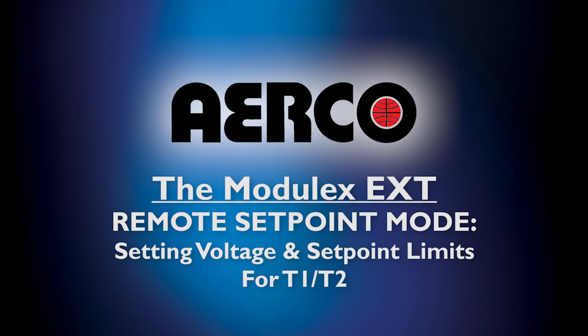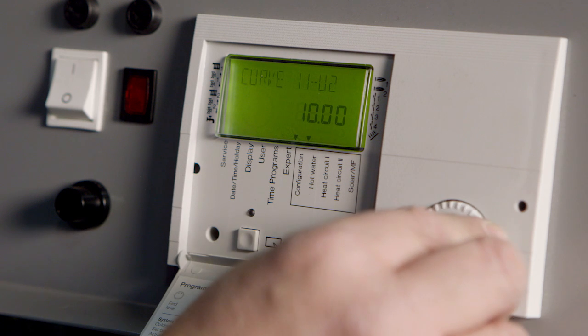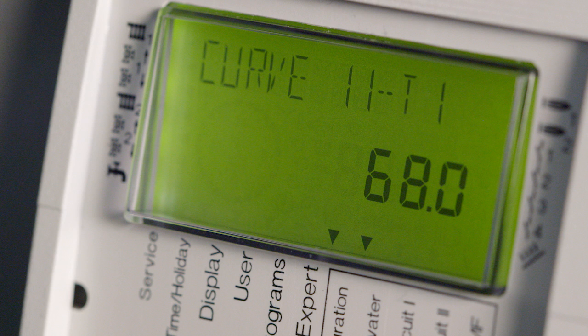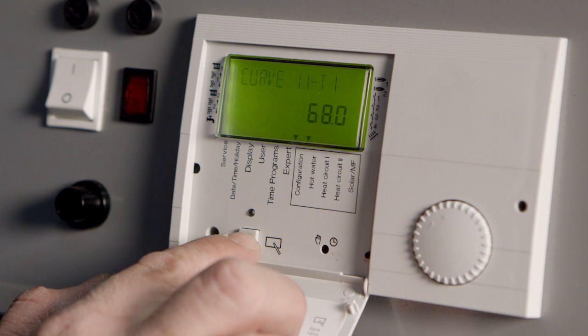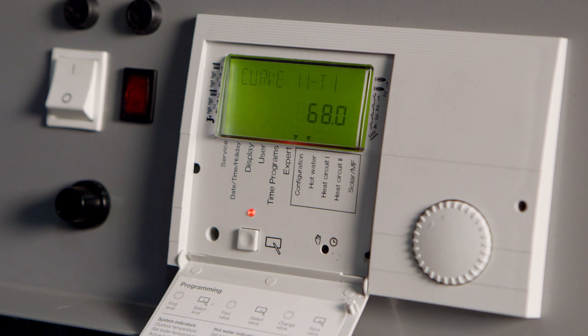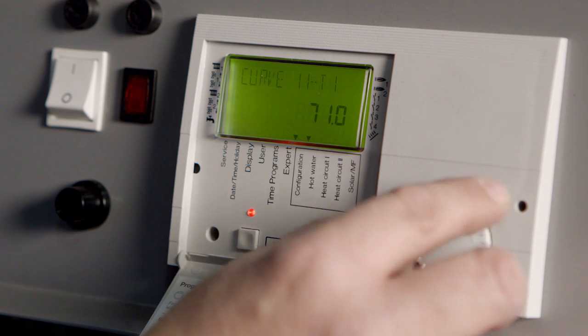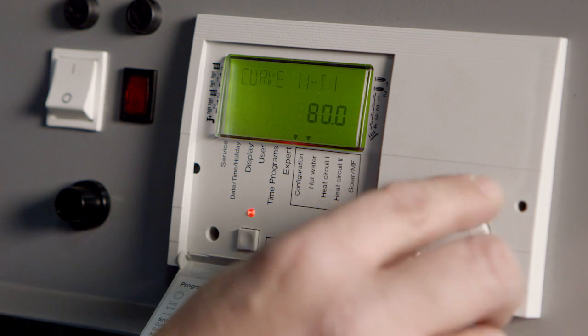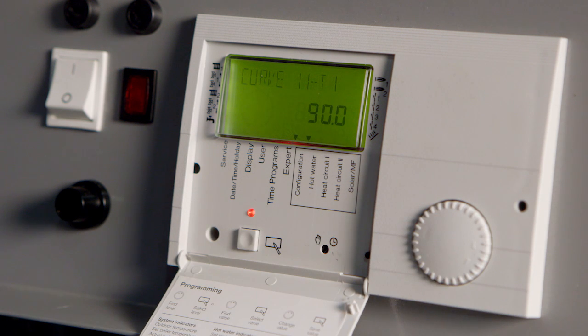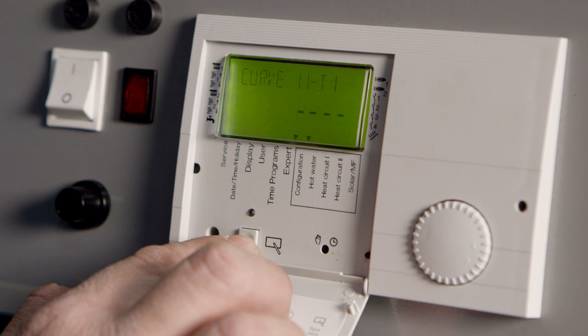Now, we'll show you how to set the minimum or T1 and maximum or T2 set point temperatures. These values should correspond with the U1 and U2 voltage levels we showed you how to set in the last video section. Turn the rotary knob clockwise and scroll to find curve 11-T1. This will be the minimum set point temperature. Press the program key. The red LED light will glow. Enter the low set temperature for T1. This value will correspond to what you set for U1. With this limit displayed, press the program key to set the T1 temperature.